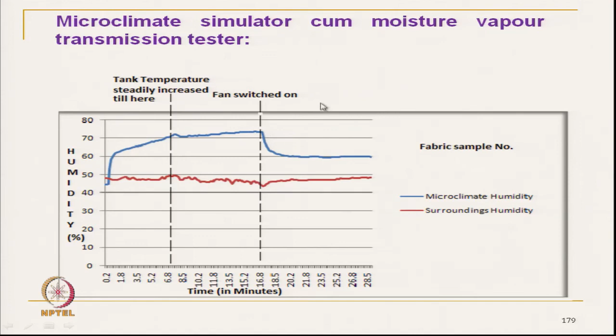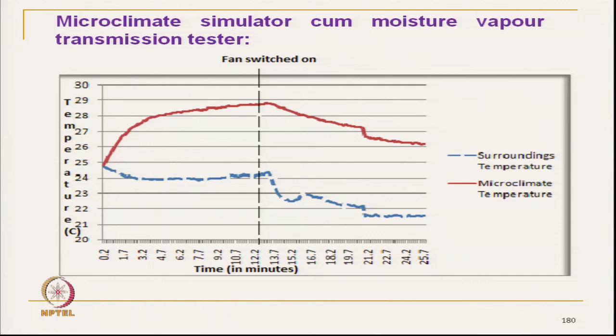The temperature of the microclimate, we have seen, increases gradually because the vapor pressure increases. So, the temperature of the microclimate increases gradually as the humidity increases. It is from 25 degrees Celsius initially at the microclimate, and it is gradually increasing. It can go further up, but as we have switched on the fan, it drops. It is dropping because of the forced convection of heat. So, this instrument measures both heat and mass transmission characteristics.